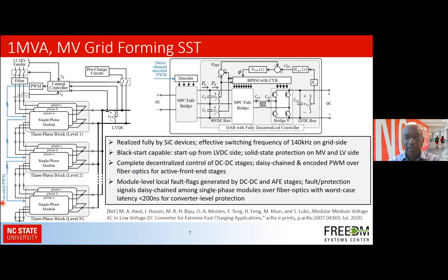So let me start with the hardware example. The key aspect of this hardware design is the startup algorithm. The hardware itself, let me just briefly tell you about it. This is a 3-phase 1 MVA unit built in a modular fashion. It has 18 modules, and each single phase module has an input front end full bridge configuration. This is an NPC configuration that makes the active front end. Then we have a DAB stage, dual active bridge stage, that also has an NPC full bridge on one side, and on the other side of the high frequency transformer is another full bridge. On the input side, these are cascadedly connected in series in a 3-phase configuration.